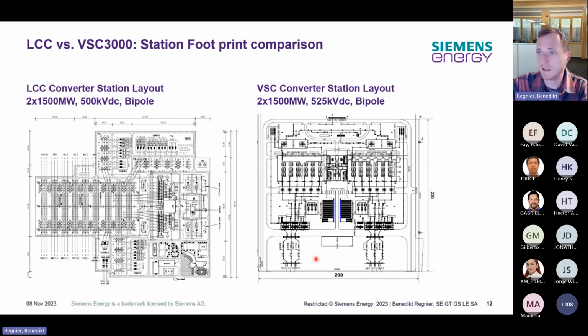Comparing that to the old LCC world, the pictures are not scaled in the same scaling. You can see here the LCC plant for a 2 times 1500 megawatt bipole would require approximately 470 by 400 meters, mainly due to all the AC filter banks that you need. And the same transmission capacity we can achieve with the VSC solution in only 230 by 200 meters. So basically it's half of it. And this makes it interesting especially if you build it close to a big city, where finding a good plot is always a challenge for our customers. So here it's very compact, and you have a very high transmission capacity.